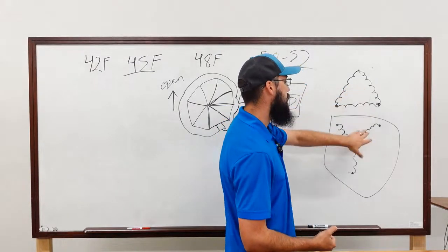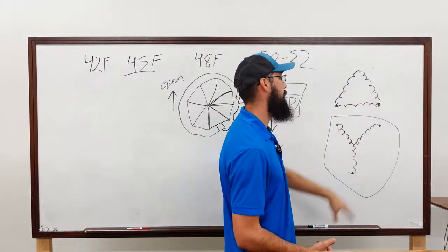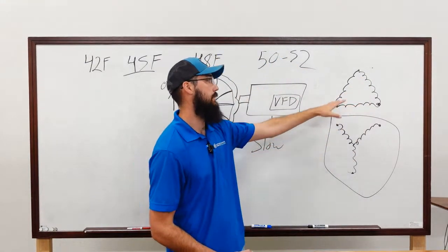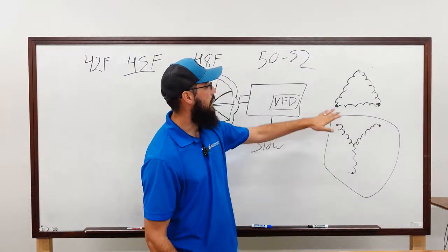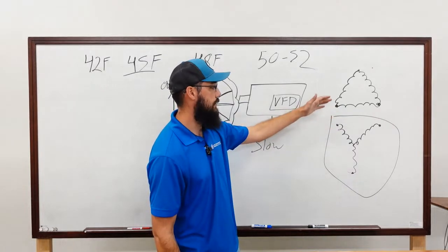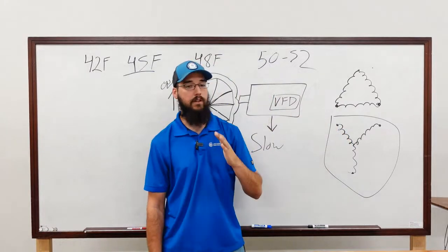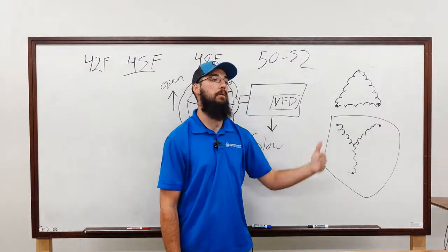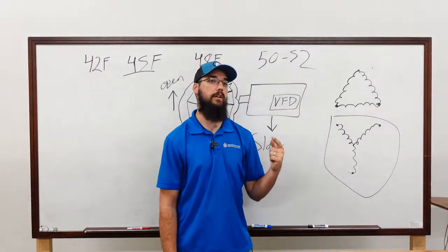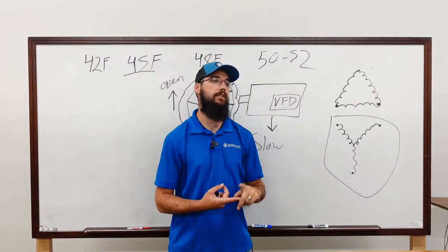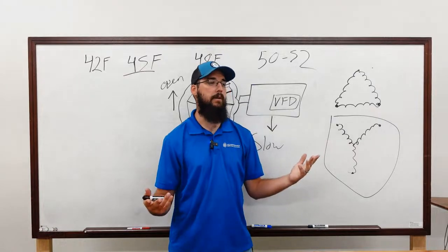Anyway, if you look at a motor tag, not every motor, but some of them, you'll see there's two different ways to configure. You can wire that motor for delta, which is the standard for us at least, and then you have a Y configuration. And this could depend on just the setup that you have. Anyway, the motor Y or delta is not dependent upon the building's power feed for Y and delta. It's based off of whether you have a low voltage or high voltage, which is what I mean by 460 or 208.